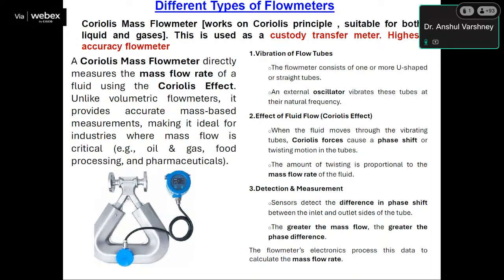Now, coming to another type of flow meter, that is the Coriolis mass flow meter. It works on the Coriolis principle and is suitable for both liquids and gases. This is used as a custody transfer meter and it is the highest accuracy flow meter being used. These flow meters come in an accuracy range of less than 0.05%. Basically, this type of flow meter directly measures the mass flow rate of a fluid using the Coriolis effect. Unlike volumetric flow meters, it provides accurate mass-based measurement, making it ideal for industries where mass flow is critical, like oil, gas, food processing, and pharmaceuticals.